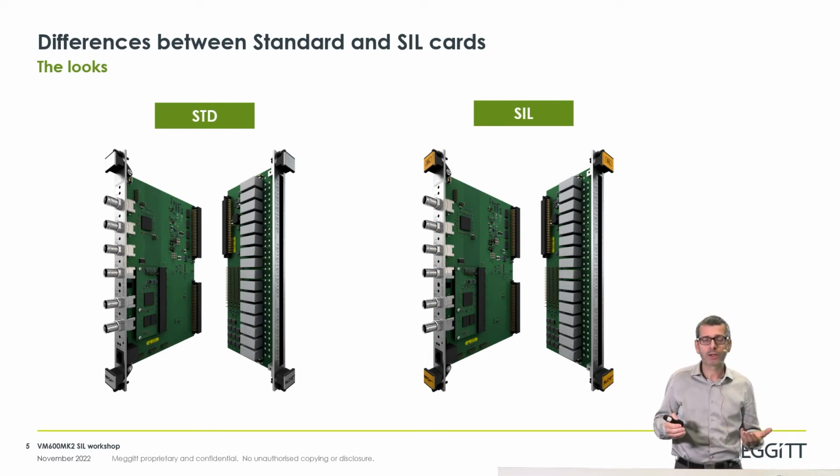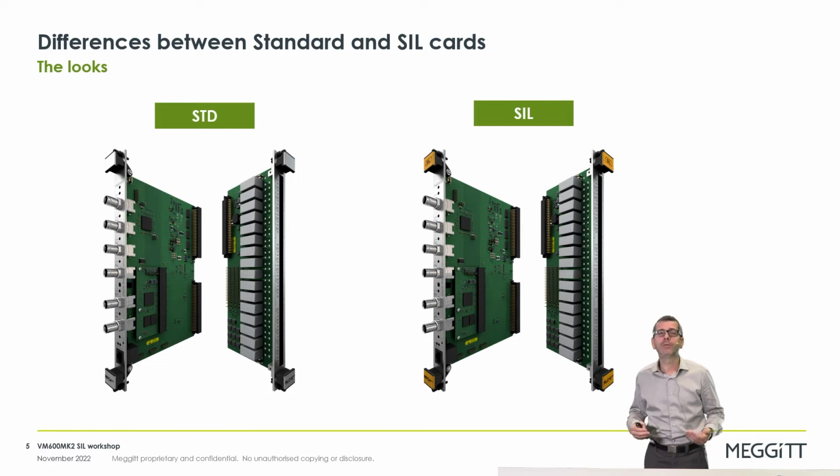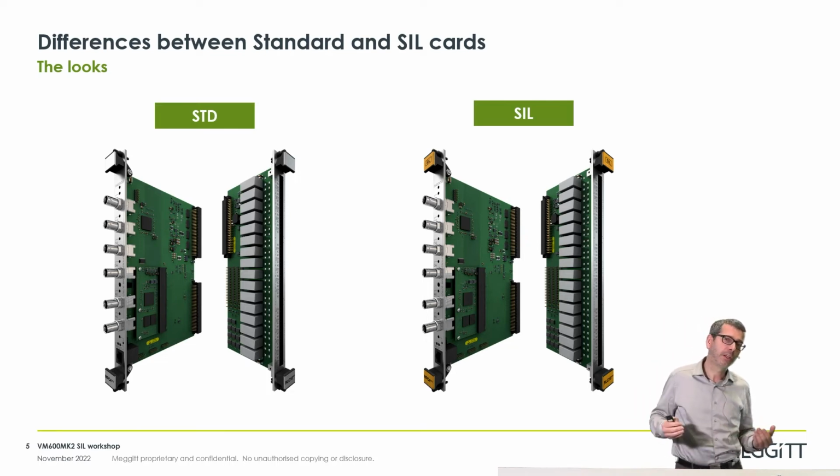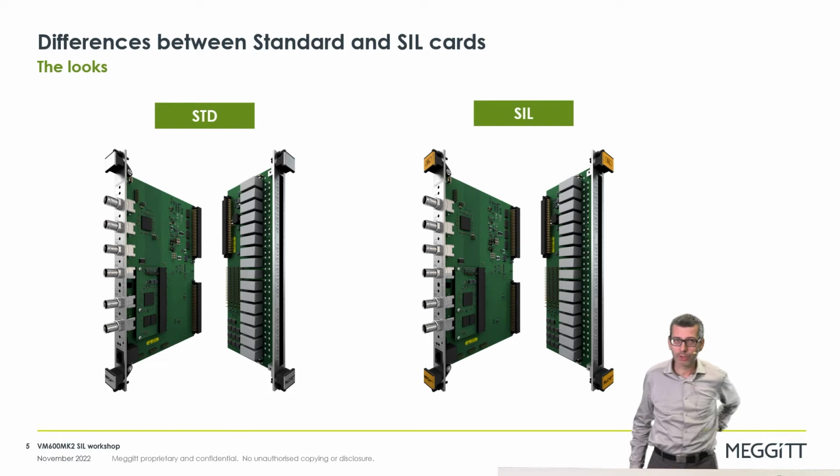On the hardware side, those two processes are running on the same CPUs, on the same memory. On the SIL version, on the MPC4 SIL, we went one step ahead, and we have segregation both on the software level and even on the hardware level. So we have separate CPUs and memory to segregate protection and monitoring.